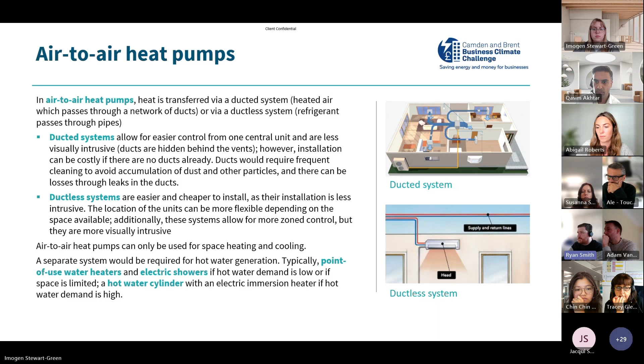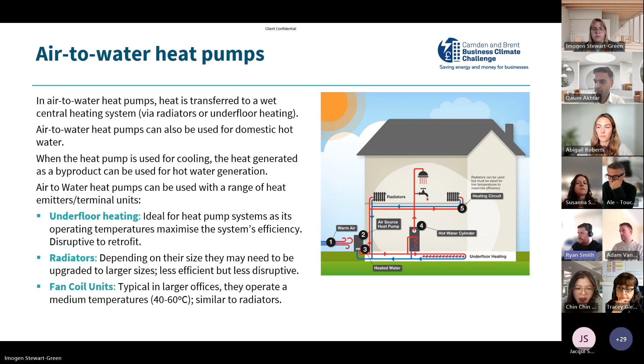So air to water heat pumps. This is more aligned with your typical heating systems, your more conventional style. So the heated water from the external unit will feed into hot water cylinder or through to the circulation heating system. This is ideal for underfloor heating because it's a lower operating temperature. Normally heating is on for longer, which is the case with underfloor heating as opposed to radiators. Radiators themselves, if they are sized on a conventional boiler, and depending on their size, they may need to be upgraded because they're less efficient, but can be less disruptive compared to something like underfloor heating. And then another option is fan coil units. So like that ducted example in the previous slide, the hot and cold water can supply the fan coil units that are hidden in a false ceiling and then provide hot or cold air to the spaces. Next slide, please.